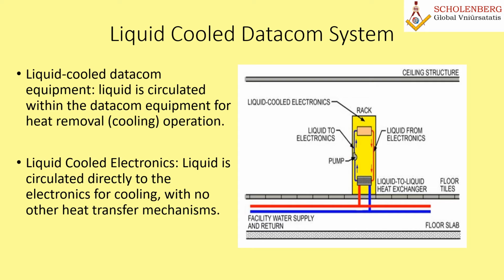Now I will explore this more, and it's very interesting, you will love to hear it. The increasing heat densities of modern electronics are stretching the ability to adequately cool the electronic components using air alone. This trend toward higher recommended air inlet temperatures, done with the goal of saving energy, exacerbates the problem. Liquid cooling is therefore becoming more prevalent. Liquid cooling is defined as a process where liquid, rather than air, is used to provide heat removal, that is, cooling. There are many different types of liquid-cooled solutions for data rooms. The most common implementations are liquid-cooled rack, liquid-cooled datacom equipment, and liquid-cooled electronics.